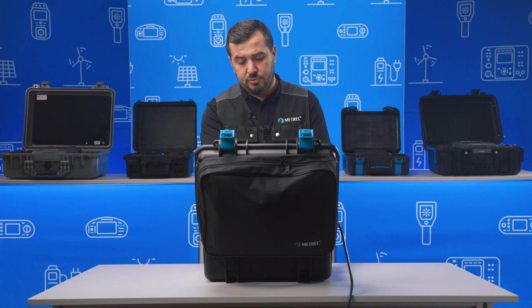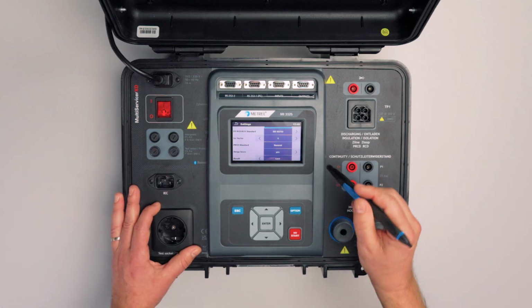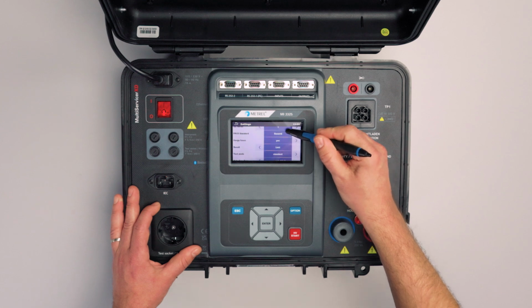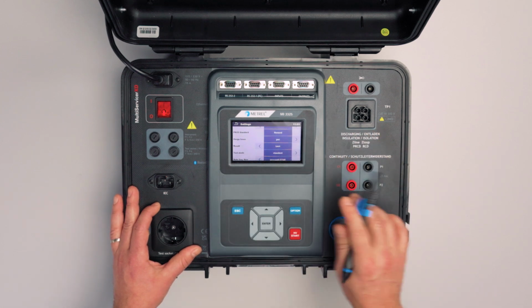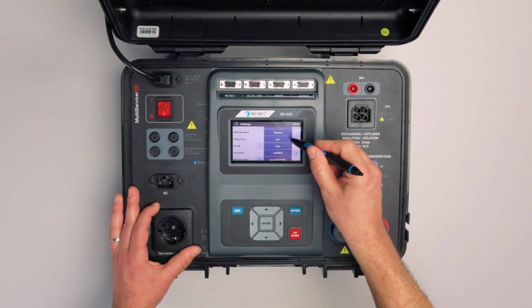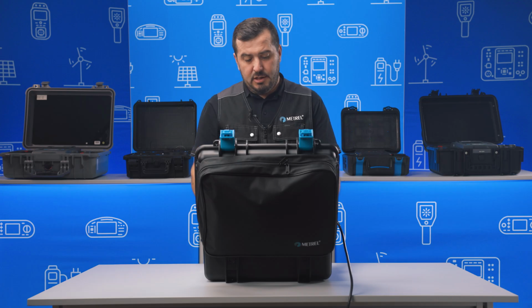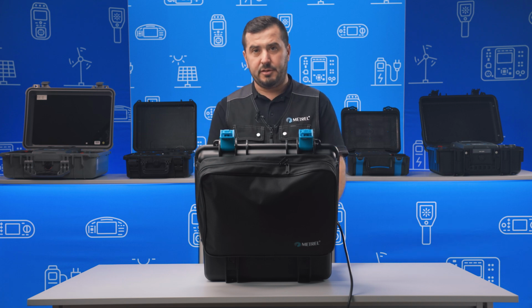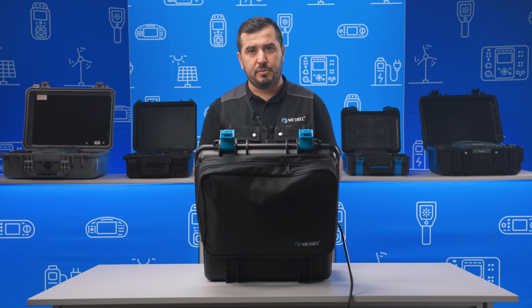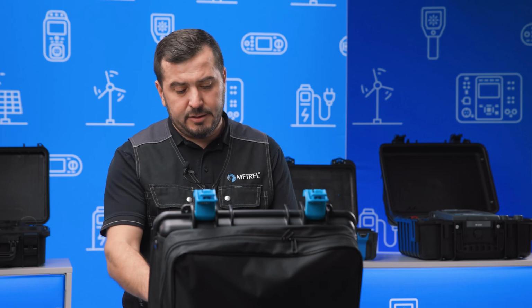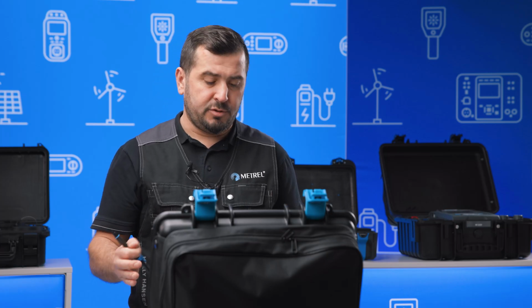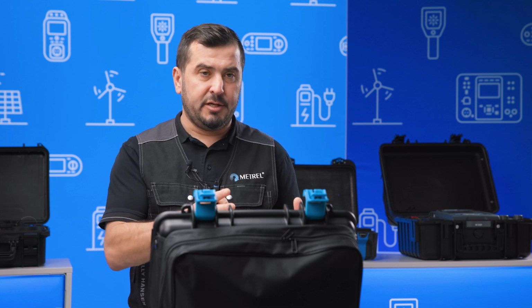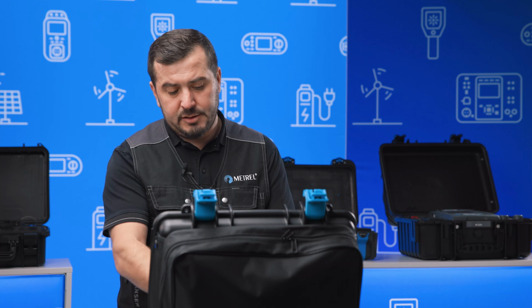Then the next option is to set the ISC factor, and the next one is the option to merge fuses. Now, maybe a few words about this option, merge fuses. As you will later see, this instrument supports a lot of different measurements, from line impedances, loop impedances, to RCD testing, of course, with different fuse settings. And if we are performing tests on the same switchboard, where of course we have mainly the same type of the fuses, we can say merge fuses.